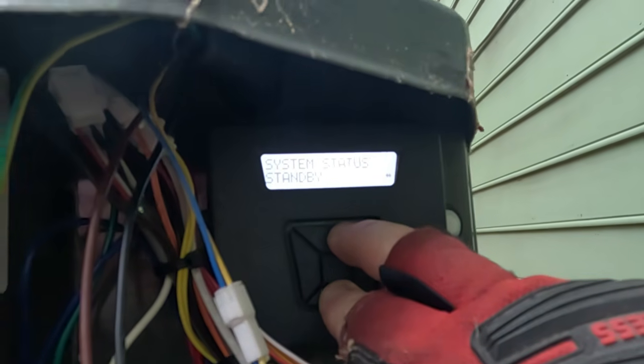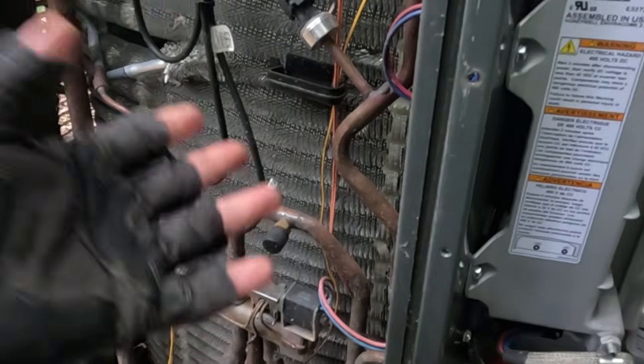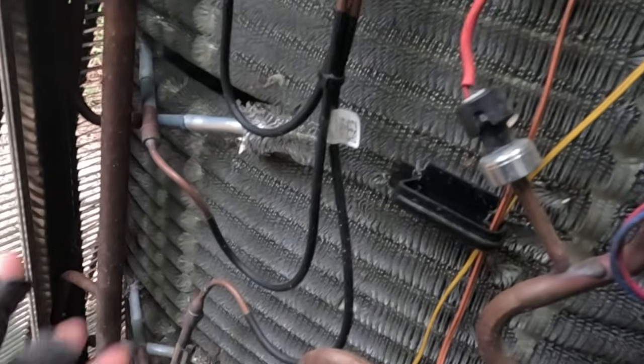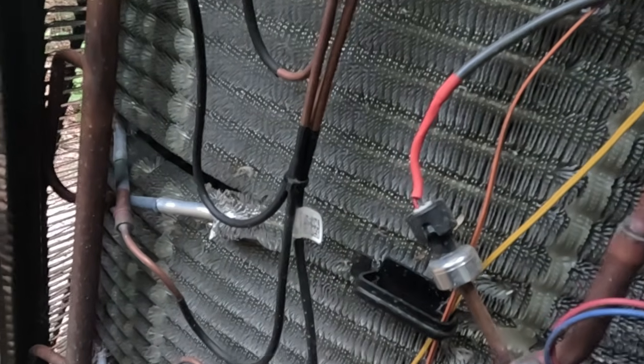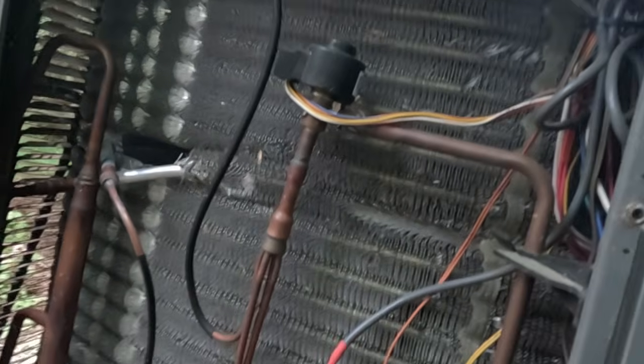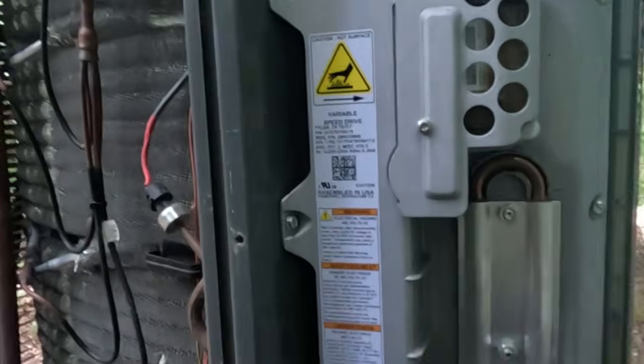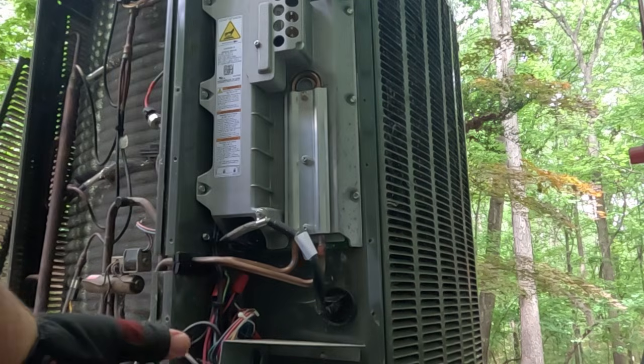So this particular Trane XV, if you go in here into the menu, monitor menu, go down to system, scroll over, this one will actually, and I don't know if you can read that on here or not, give you your coil temperatures. Oh, there's our suction line temperature sensor reading 0 right there, and then it gives you your suction pressure, and it'll measure your superheat and subcooling on this. You don't actually have to hook gauges to it. Once that fault's cleared and this thing's on and running, you can go through there. It'll tell you high pressure, low pressure, superheat, subcooling on this outdoor unit. Sensors inside do the same thing for cooling mode. This one will do it in heating mode. It also gives you your superheat while you're running and cooling, if you need to look at all that and check it without putting gauges on it.